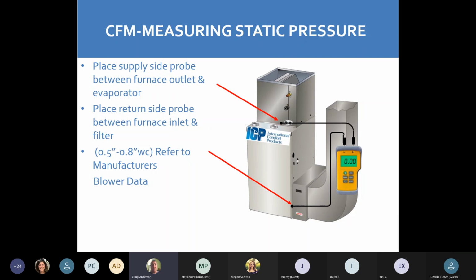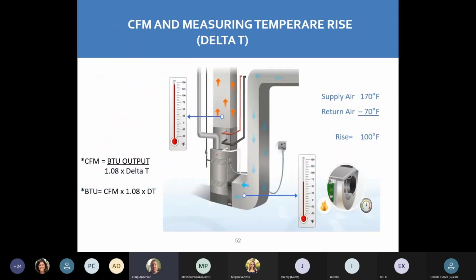Static pressure takes nothing to check. Get the proper instrument, throw it in the supply and the return, let the unit run 15 minutes. Let's see if our airflow is good. Temperature rise, same thing, whether it's in heating or cooling. Let's see what our split is between our return air and our supply air. That could save us heat exchangers down the road. That could save us freeze up in coils. It's going to tell us what's going on in that ductwork.